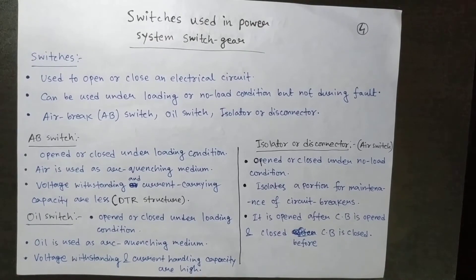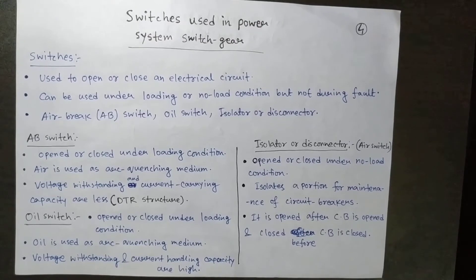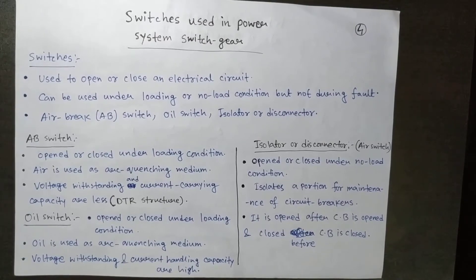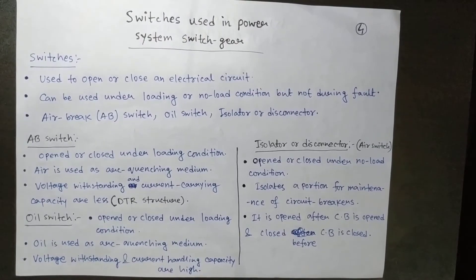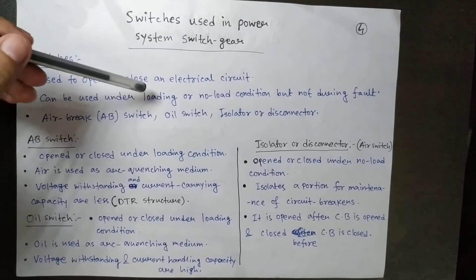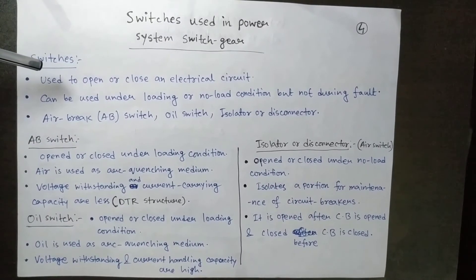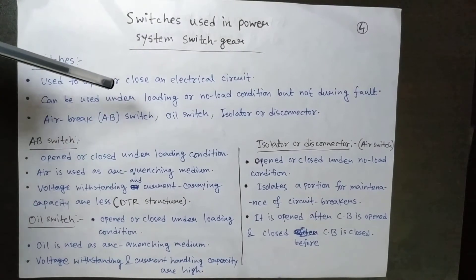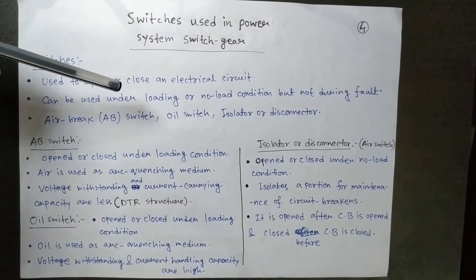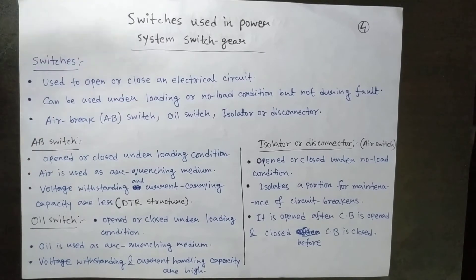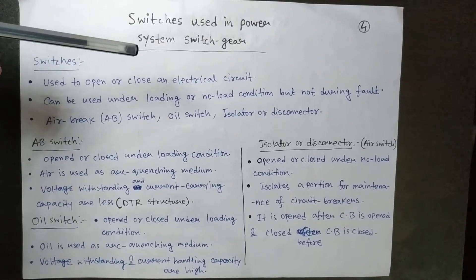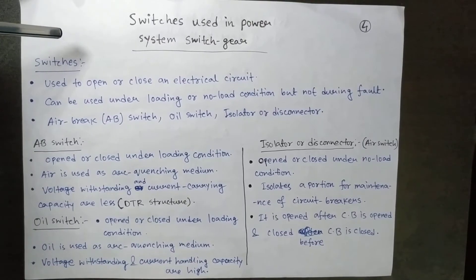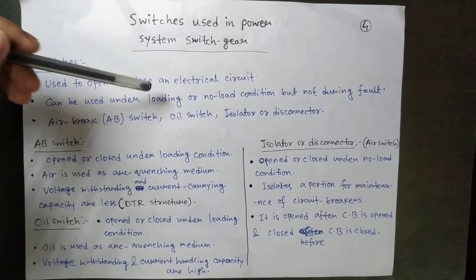Switches are one of the major parts of switchgear. There are different kinds of switches used in power systems for switching purposes. A switch is used to open or close an electrical circuit. It can be used under loading or no-load conditions, but not during a fault. For fault conditions, circuit breakers are used — switches are only for normal operating cases.